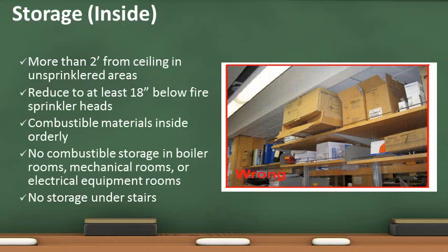Interior storage shall not be within 24 inches of the ceiling in buildings without sprinklers. In buildings with sprinklers, storage is not permitted within 18 inches from the bottom of the sprinkler deflector. Storage should always be neat and orderly, and it is not permitted under stairs.